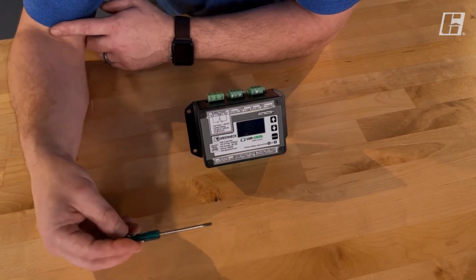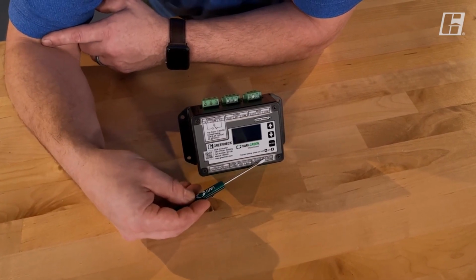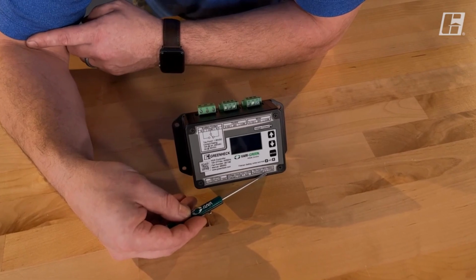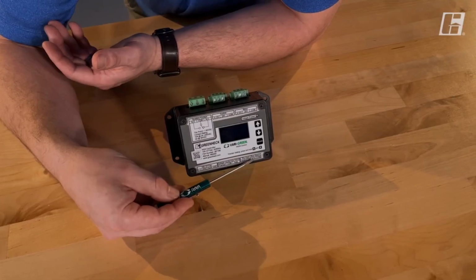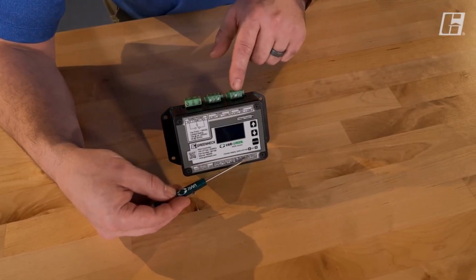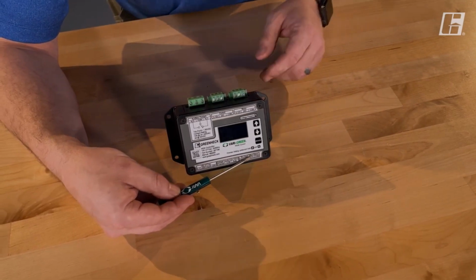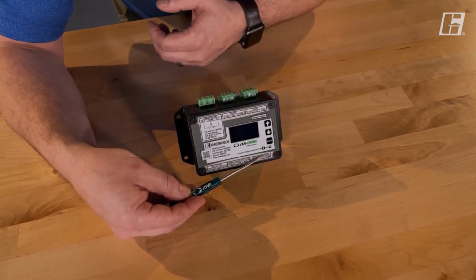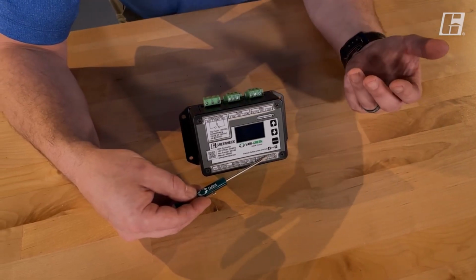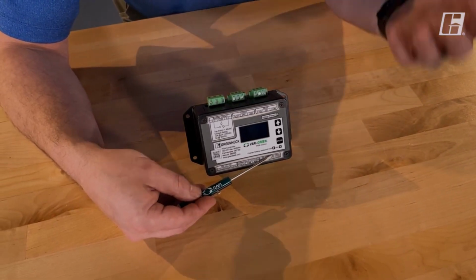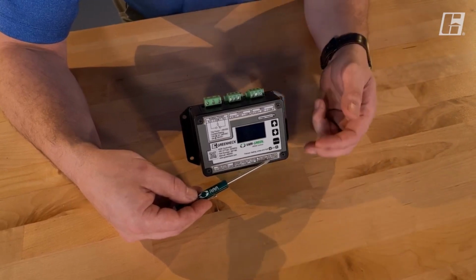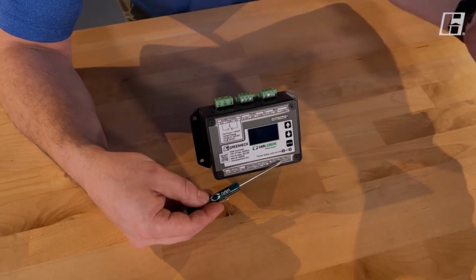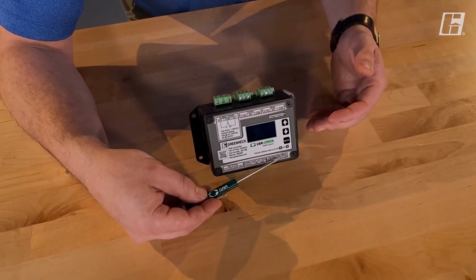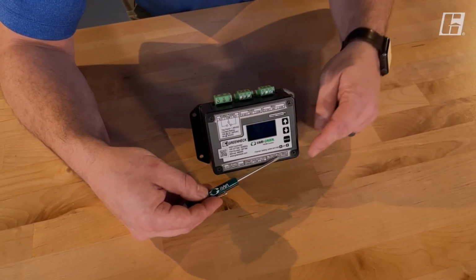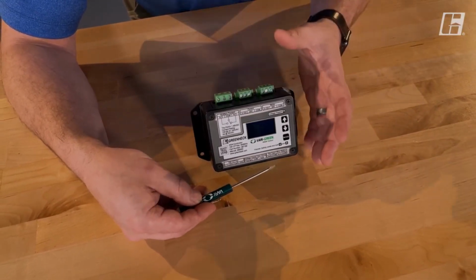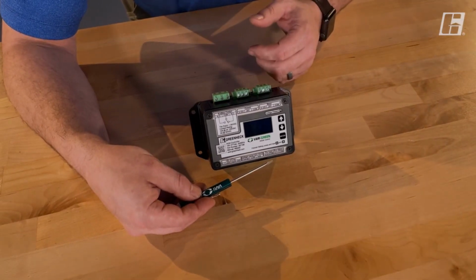Now just a couple of terminals left. On the end here, we have run status. This again is a dry contact. This contact closes anytime a 2 to 10 volt signal is being sent to the motor. I can use that run status to send information back to a building management system saying, hey, this fan is being told to run right now. I can also send that to a makeup air unit, or I can send it to another HOA. So I can use that as information to say, hey, this fan started, you should start too.